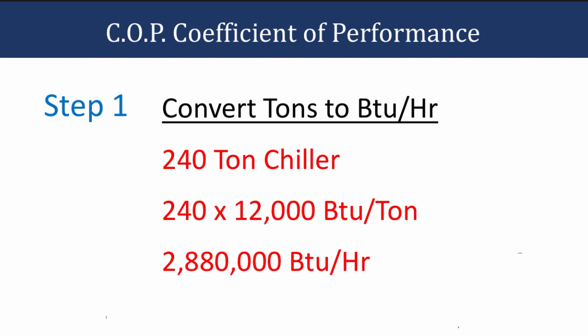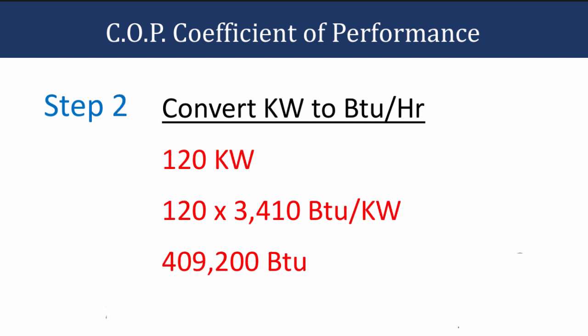We have a 240-ton chiller. We know there are 12,000 BTUs for every ton, so 240 times 12,000 gives us 2,880,000 BTUs per hour of output. Now we convert the input power — we're using 120 kilowatts to produce that output. We take our kilowatts times the conversion factor of 3,410 BTUs per kilowatt, which gives us 409,200 BTUs per hour.